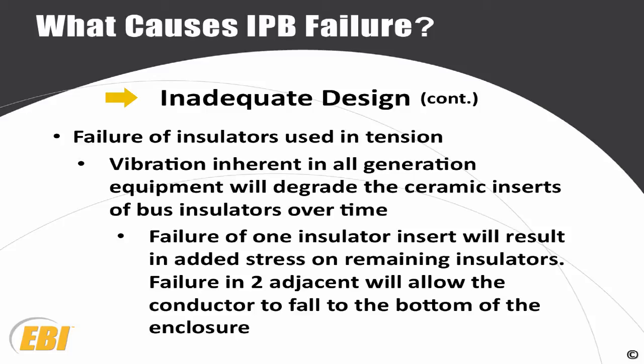We also have a bus manufacturer that uses a lot of the support insulators inside the bus, and they will actually turn their design upside down when they go inside of a building, where the support insulator is supporting the conductor from underneath the conductor outside because it's sitting on steel outside that's underneath the bus. The steel on the inside of the plant is above the bus, so they just turned the entire assembly upside down. So then you have a conductor that's hanging from the insulator.